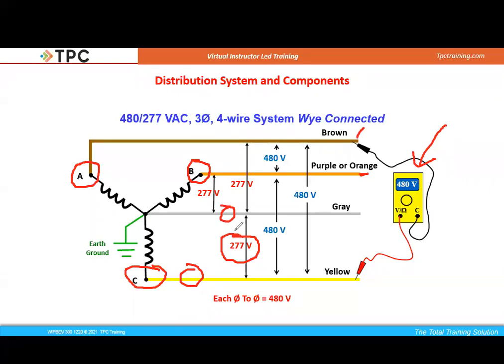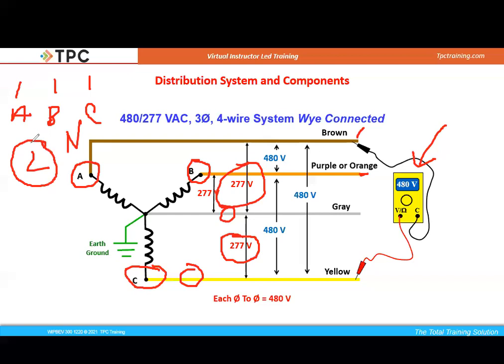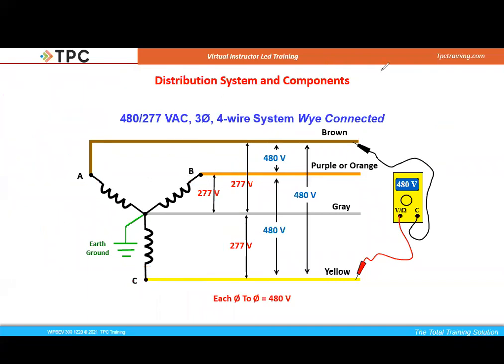For instance, if we're working on those lighting circuits and they are 277 volts and they utilized all three phases, in other words, my first room is on phase A, my second room might be on phase B, and my third room on phase C, and we are doing a light somewhere, that neutral could be shared by all three phases. And when we're trying to work on this light, no matter what it is, we want to make sure we lock and tag out all three phases because I am going to tell you right now, 277 volts hurts, and it's not a good voltage to try to mess with a whole lot.